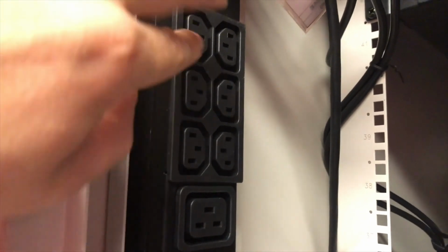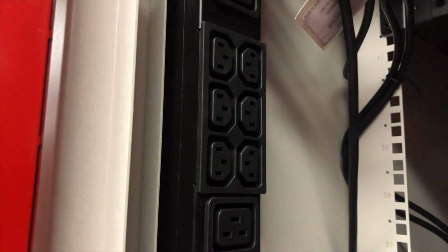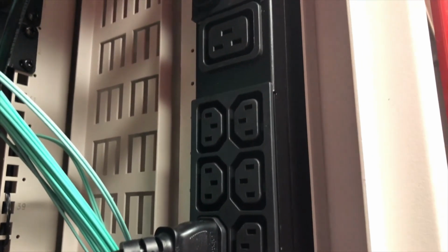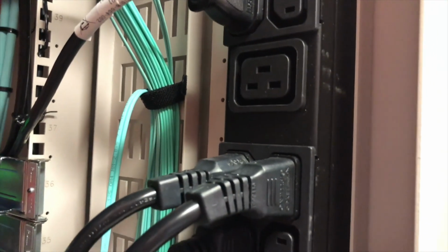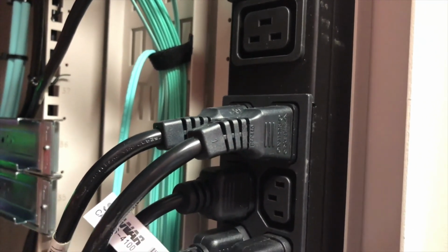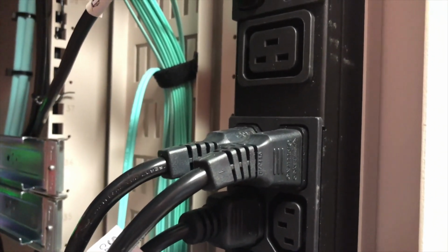Because what you'll find is a lot of devices, a lot of newer server switches, etc., will have dual power supplies. So you can run one into the left-hand side and then one into the right-hand side, so that if one power adapter fails, you've got redundancy. And if a whole particular rail of power fails, you've got redundancy also. So you've got the other side just like so, nice and easily running connectors straight into the sides for redundancy of power.